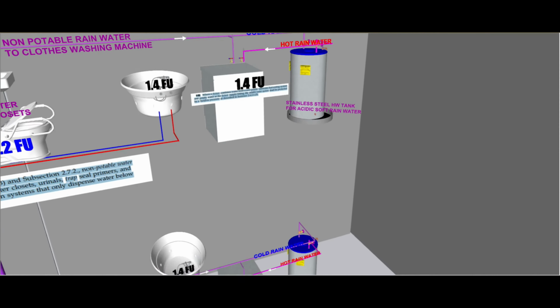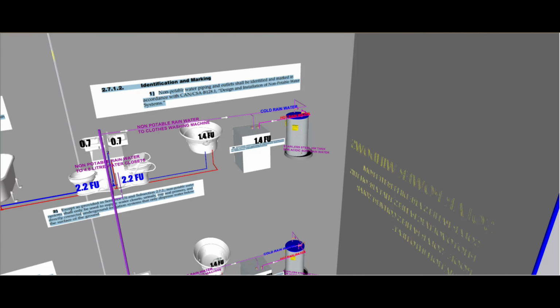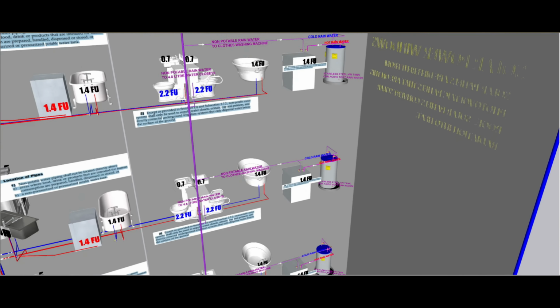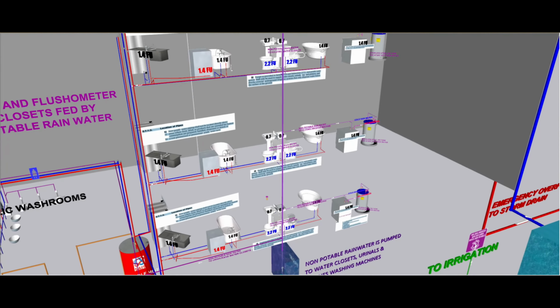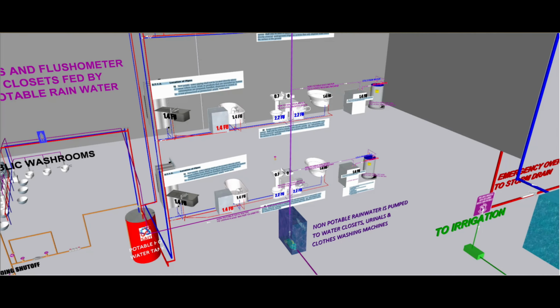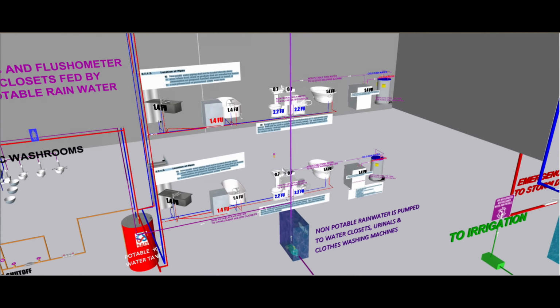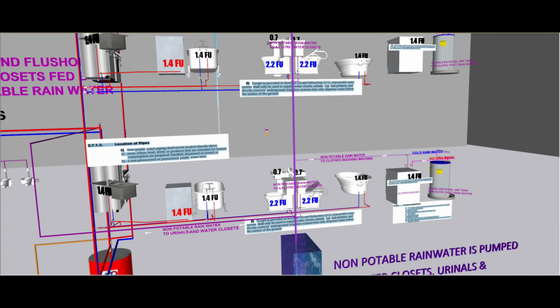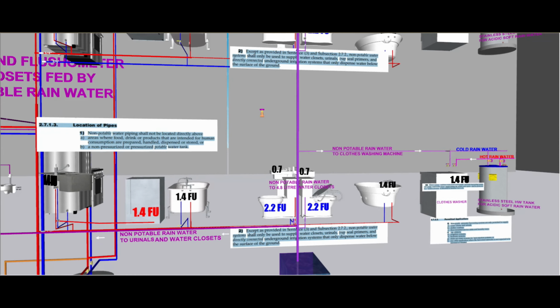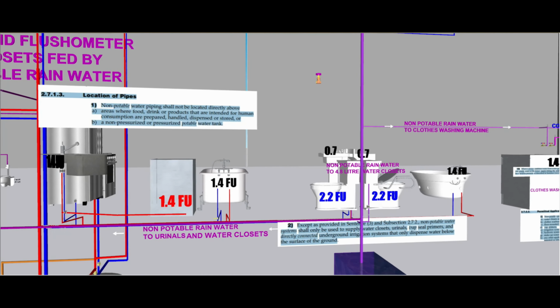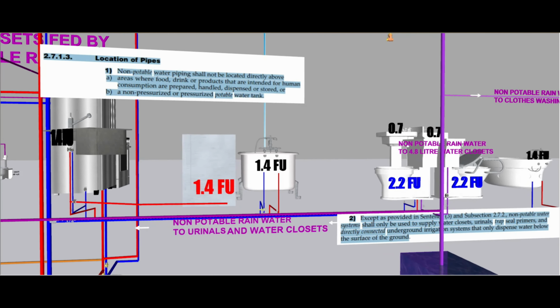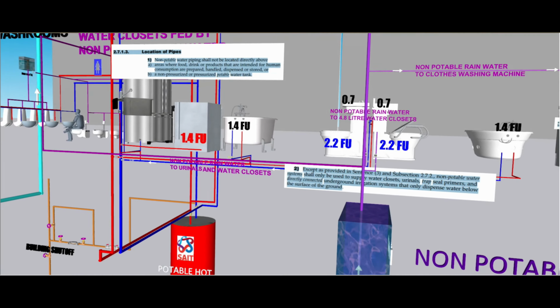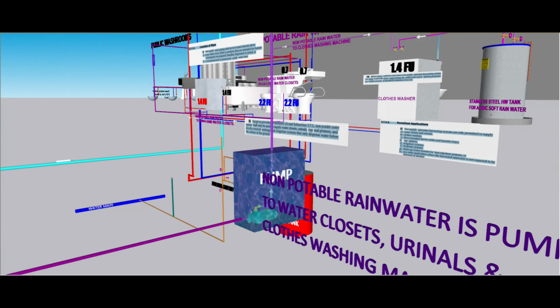Now notice I've installed 4.8 liter water closets, which aren't even in our new 2020 code book, but they are the current ones we sell now. So we'll probably change the fixture unit rating on these - they might be lower later, but that's unknown yet. So if you follow the purple main, which is the rainwater, all the way up to the 7th floor, you'll notice that all the toilets are being fed with rainwater as well as the washing machines. And that should work pretty good, because washing machines and toilets use quite a bit of water. They figure this will help out with 50 to 60% of your water use in this building.